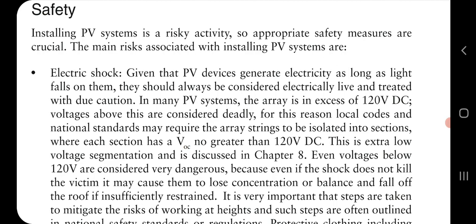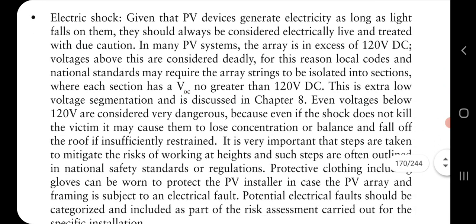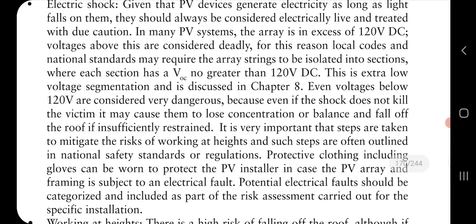So the national standards or local code should be made in such a way that no DC string is more than 120 volt DC, and it should be handled very carefully while installing. In this one, the workplace has to be considered, proper protective clothing has to be included, gloves have to be worn, to avoid all this risk.